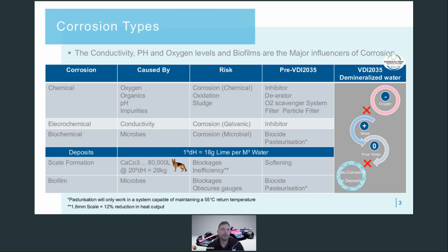Deposits, though, can also be problematic. Most of you will be familiar with lime scale. 1 degree of carbonate hardness holds up to 18 grams of mineral lime per meter cubed. In an 80,000 litre system, this is 28 kilograms, or the equivalent of that German Shepherd dog there, clogging up your heat exchanger. 1.6 mil of scale also gives a 12% reduction in heat output. So removing hardness from the water is vital to maintain energy efficiency and reduce blockages.